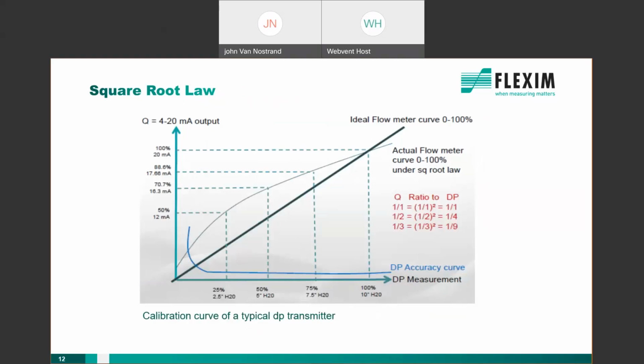So the primary element itself has a fixed error that cannot be less than 1% as per ASME. The transmitter uncertainty is an addition to that error. So this is a best fit picture that illustrates a typical accuracy. It's called the best fit curve for a DP transmitter that has a range of 0 to 10 inches of water, which is quite common. In the red, you can see the ratio of DP to the flow is 1 at 100% of the span. So it's nearly perfect. 1, and if you take the square root, that's shown there in red, the square root of 1 is 1. So it's most accurate at 100%.